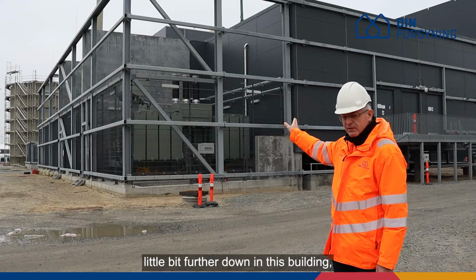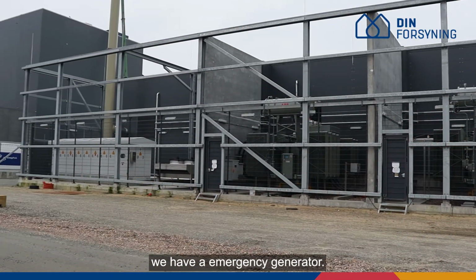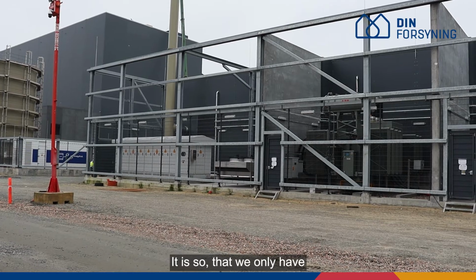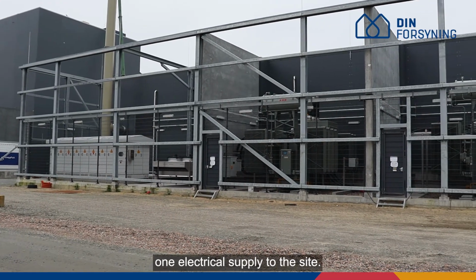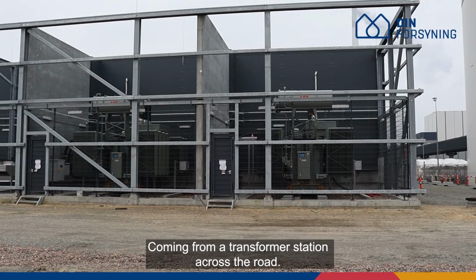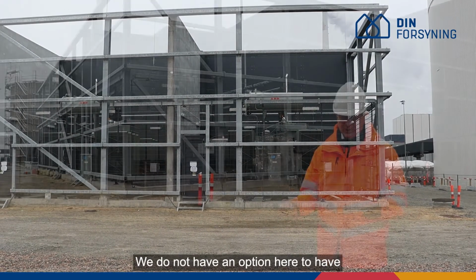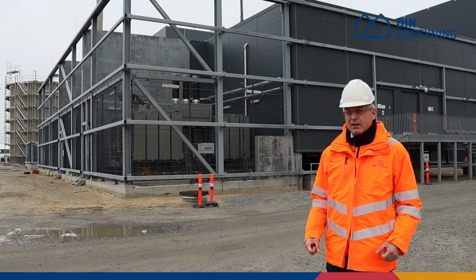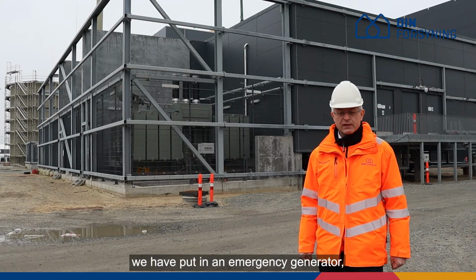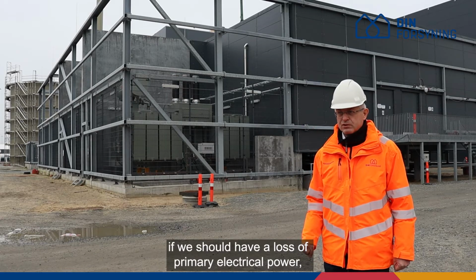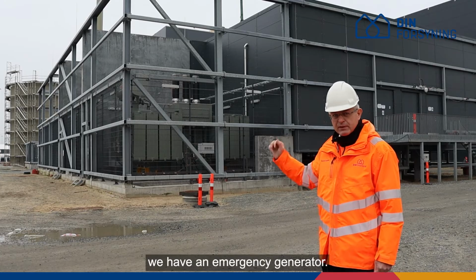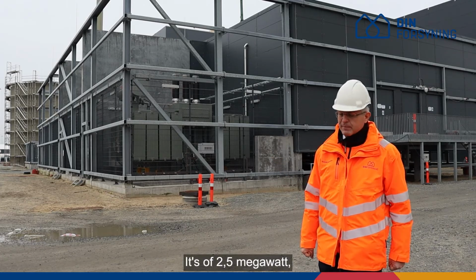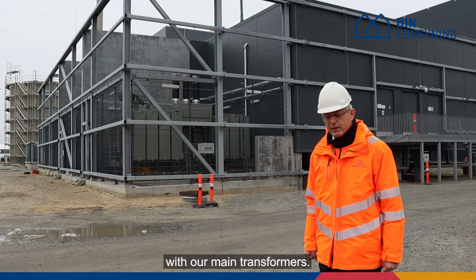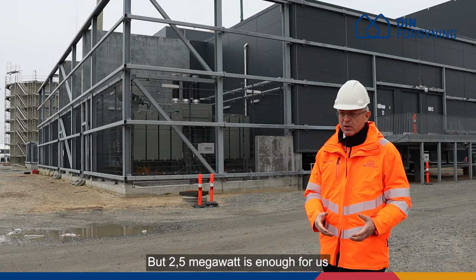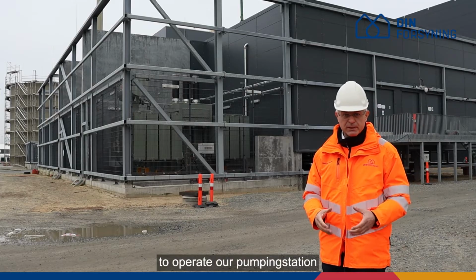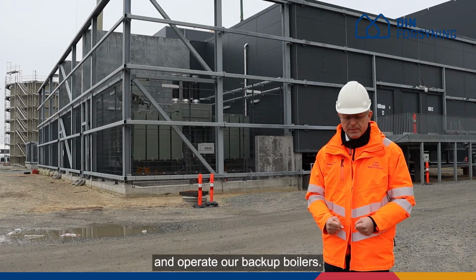Furthermore, a little bit further down in this building, we have an emergency generator. It is so that we only have one electrical supply to the site coming from a transformer station across the road. We do not have an option here to have two independent feed-ins. For that reason, we have put in an emergency generator. If we should have a loss of primary electrical power, we have an emergency generator. It's of 2.5 megawatt, whereas we can put 50 megawatt in with our main transformers, but 2.5 megawatt is enough for us to operate our pumping station and operate our backup boilers.